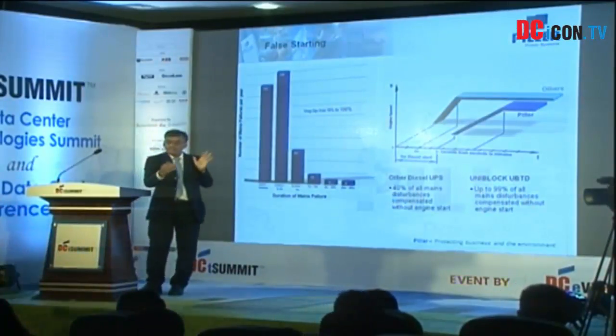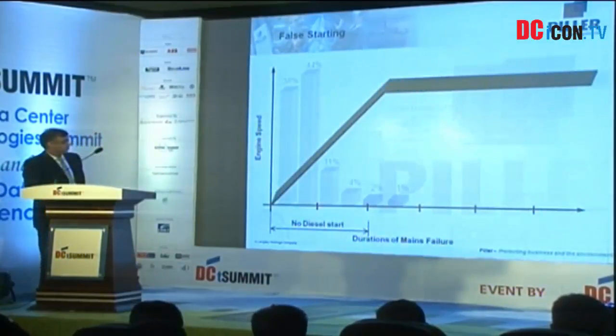So that's the concept behind the flywheel that Piller has, so that you can extend the life of your diesel engine and maintain it at very low cost. This particular advantage is very unique only to Piller and not to our competitors, because of the technology that we have, because of the flywheel that we have. If you see here, this shows the number of diesel starts with Piller as against the diesel starts with a competitor's similar diesel rotary UPS system. So Piller's diesel rotary UPS system starts less, thereby giving you an advantage on the overall maintenance cost.